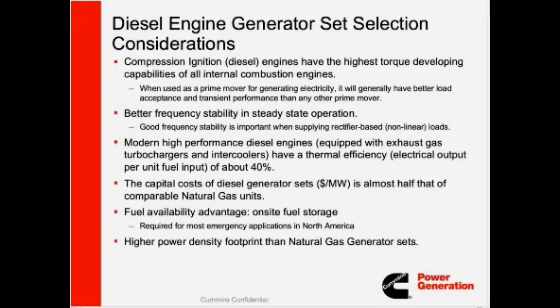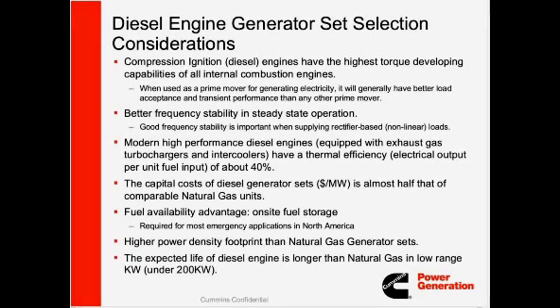Higher power density footprint than natural gas generator sets is also expected with diesel generators. They're smaller. For example, for a 2 megawatt diesel generator, it's going to take less space and be lighter than an equivalent 2 megawatt natural gas genset. The expected life of diesel engines is longer than natural gas for low range kilowatts and under 200 kilowatt size ranges. So there are many advantages of diesel generators, and mainly it is the preferable source for emergency and standby applications.